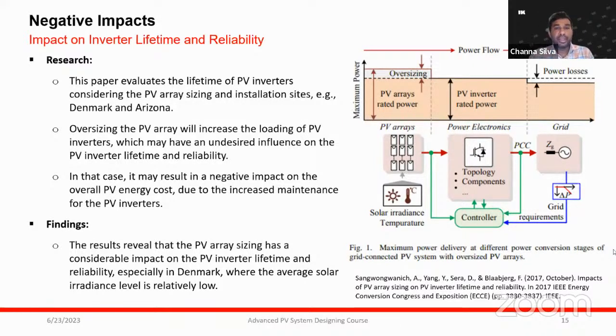So what would be the negative impacts? Probably one study I found from research was done for Denmark. What exactly it showed is that for lower irradiance levels, the inverter's lifetime and performance will be much lower with too much oversizing. Maybe they selected some specific inverter, so in that case it reduced the lifetime and the reliability. As I said, when it comes to inverters, they specifically mention the maximum DC input power they can have. For example, let's say small-scale inverters.